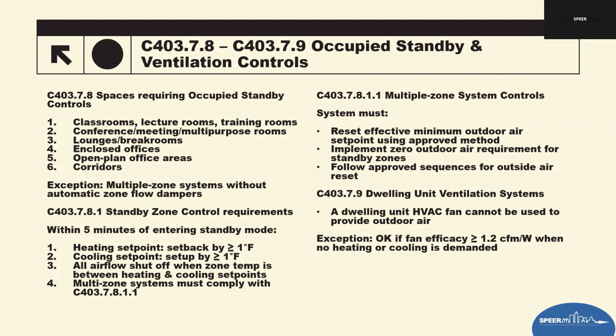So 403.7.8 says where occupied standby is required. The code lists specific spaces that must have standby controls. These are areas with intermittent uses such as classrooms, meeting rooms, break rooms, offices, and corridors. The intent is to reduce energy use when occupant sensors indicate the space is empty. So it's not just lights anymore, it's also the HVAC systems. Importantly, if a space is part of a multi-zone system without automatic dampers, it is exempt because the airflow cannot be individually controlled for just that one unit.